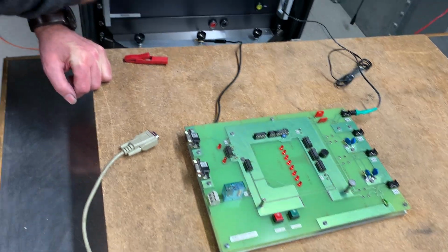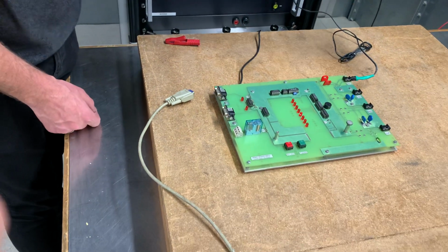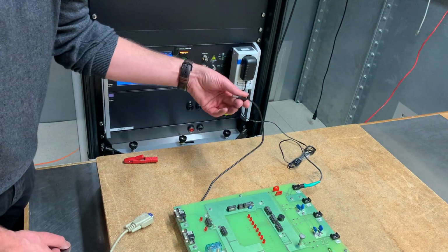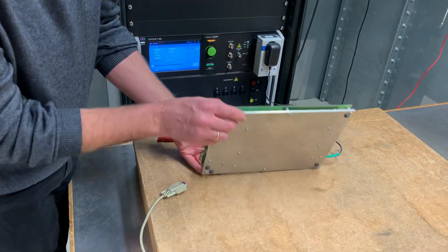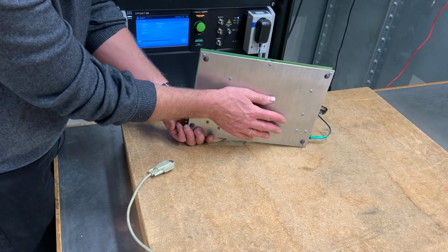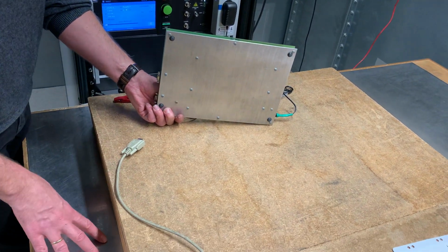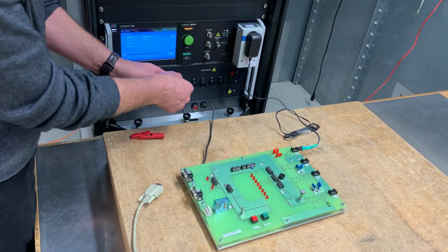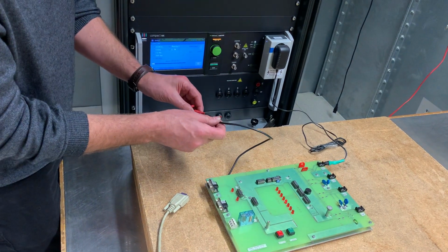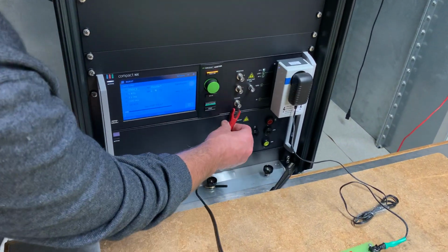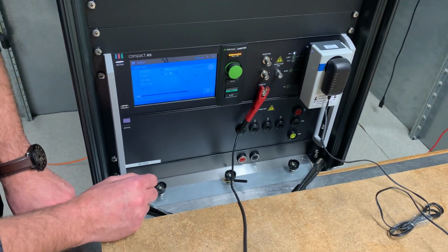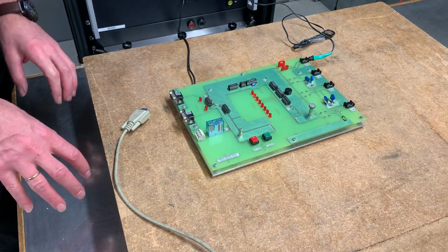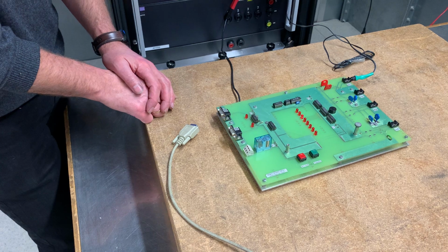So again, I will stop the disturbances. Please power the board with the DC power, with that power supply unit. Take care to ground the board. That is, let's say, the ground plane. If you have got no test bench with a ground plane, then simply use this one on a normal table. Connect this one to the test generator. In this moment, for example, over a connector in this way, simply to ground of the test generator, and then do the test. That could also be a way when you have not got a whole test setup.